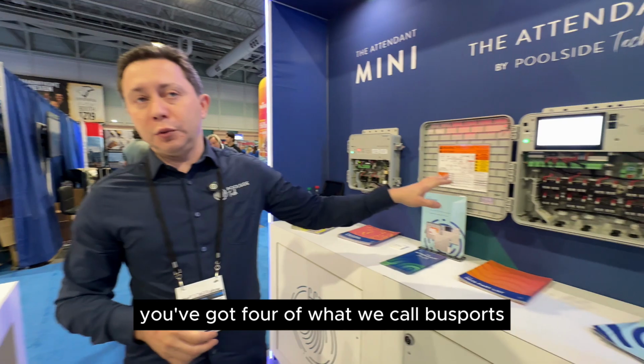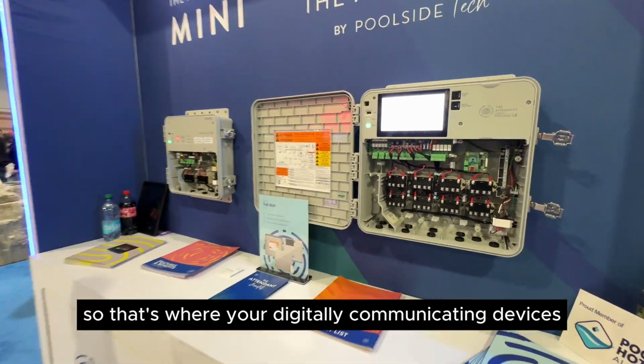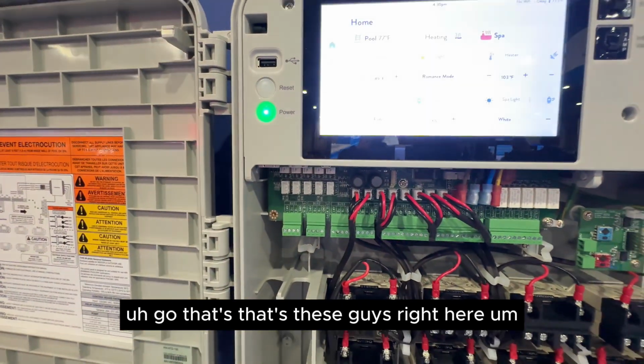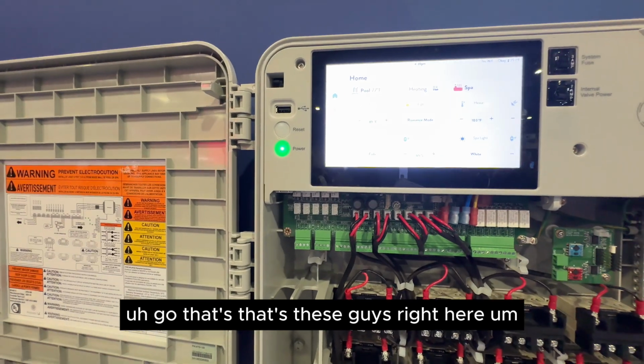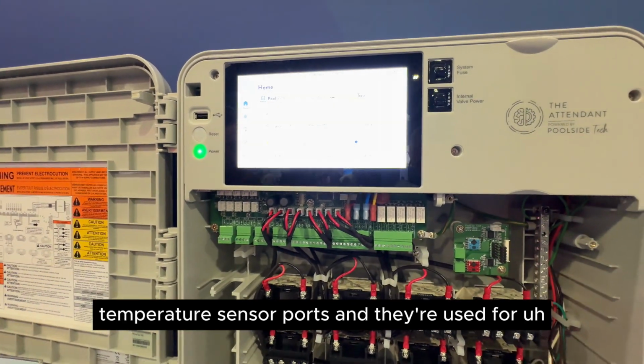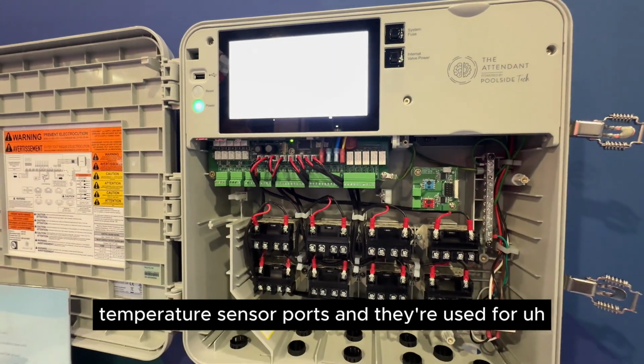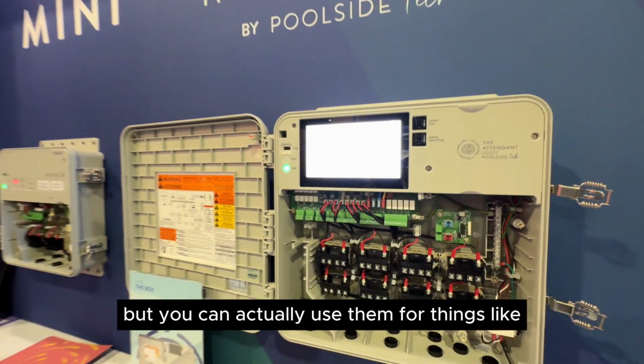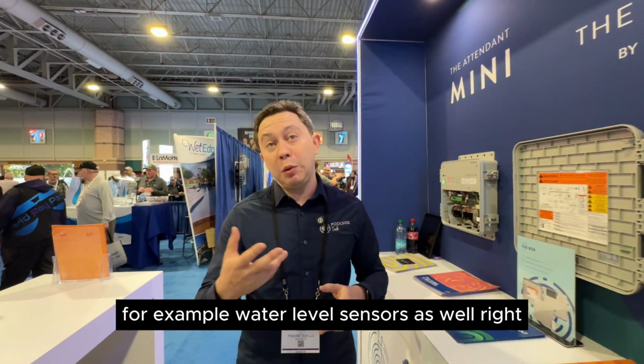You've got 4 of what we call bus ports, so that's where your digitally communicating devices go—that's these guys right here. Up to 5 temperature sensor ports, and we call them temperature sensor ports, but you can actually use them for things like water level sensors as well.